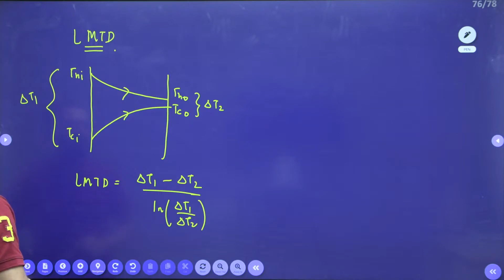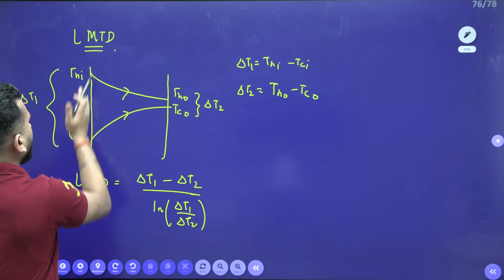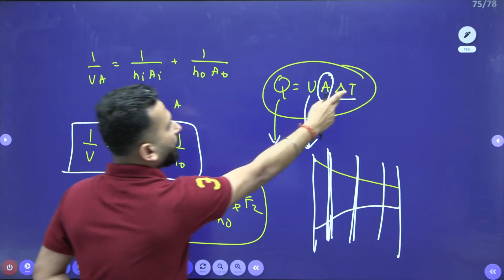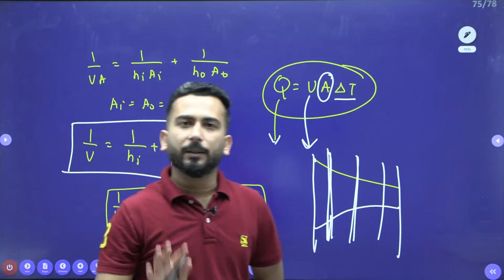What is delta T1? The delta T1 value is THI minus TCI. What is delta T2? The delta T2 value is THO minus TCO. So you have the temperature difference at the inlet, delta T1, and the temperature difference at the exit, delta T2. You get LMTD, and after finding LMTD, you put it over here. A, Q you know, U you know, so you can very easily find the value of A, the size of the heat exchanger.